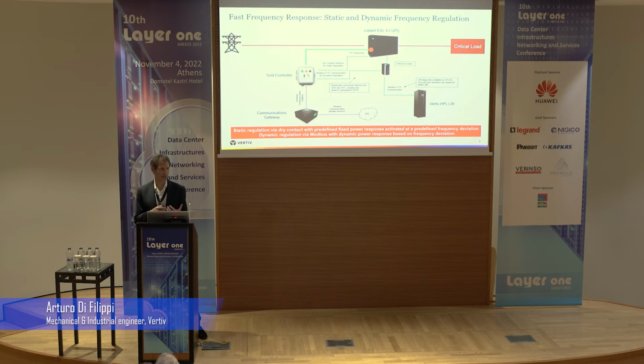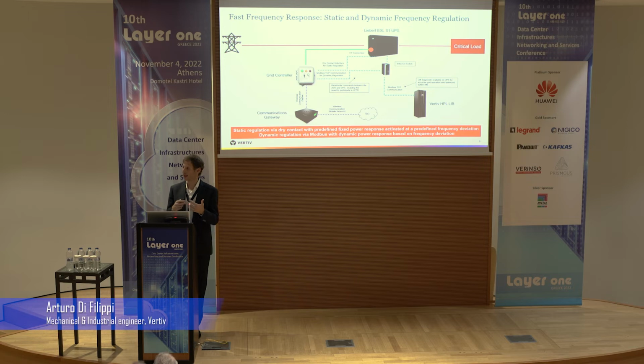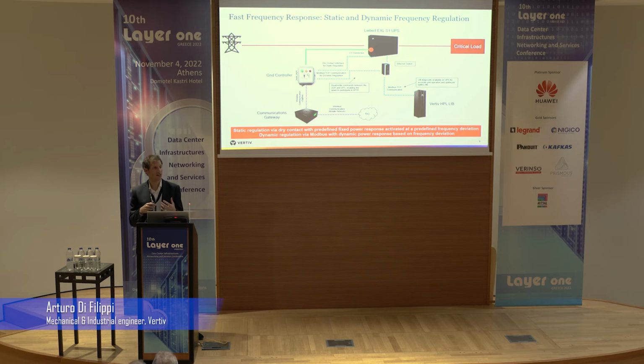One of the challenges or barriers we've encountered is that some operators say: since I'm using the batteries not just for backup but more extensively, maybe a few times per month, the life of the battery will be affected by this high cycling, leading to enhanced degradation. So we are providing a tool that can verify the degradation of the batteries if you use them for these services, like peak shaving, such that the TCO at the end and the business case will be positive for the customer.